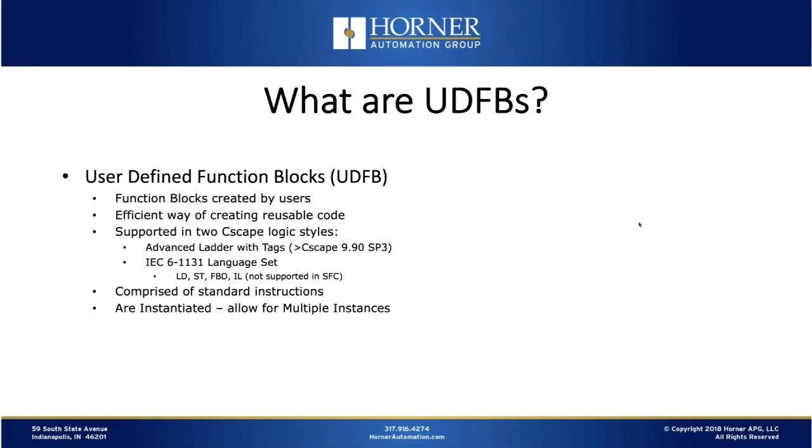Now, the logic within the function block is comprised of standard instructions, whether those are Boolean instructions or, again, other function blocks, or even other user-defined function blocks can be embedded in a UDFB. One of the key features of UDFBs is that you can use multiple instances of them scattered throughout your code. They're instantiated, as they say.